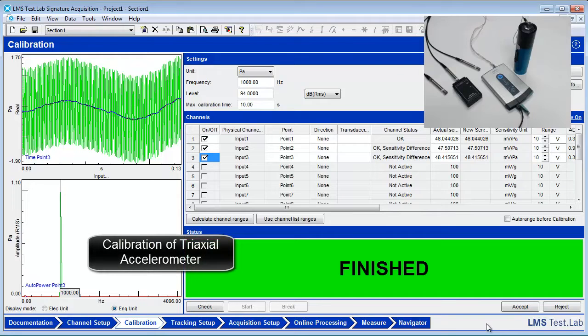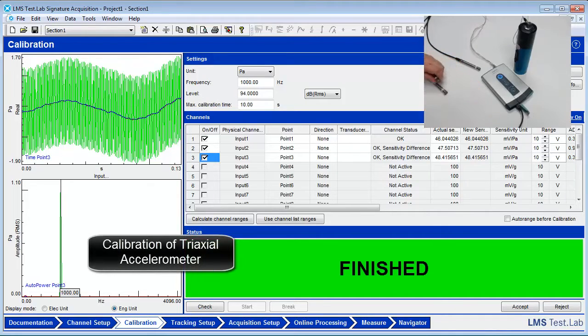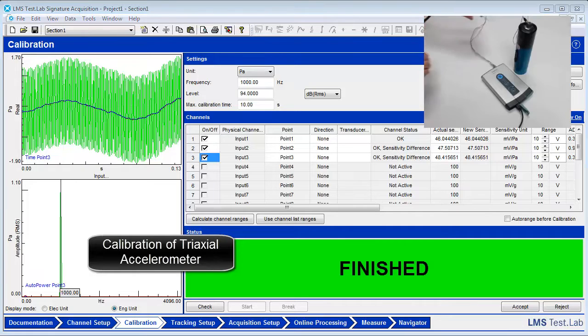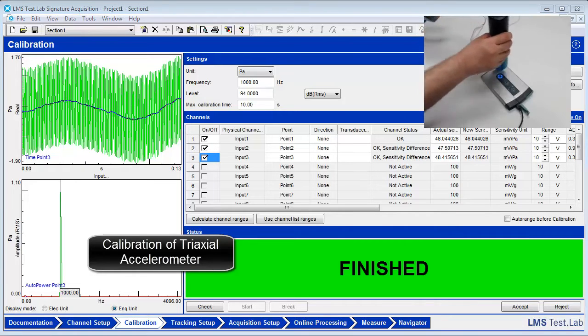To complete the calibration of a triaxial accelerometer, attach the accelerometer to the SCADAS front end through the dynamic input channel using the appropriate cables.